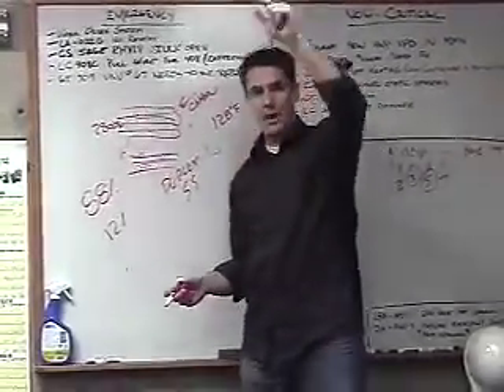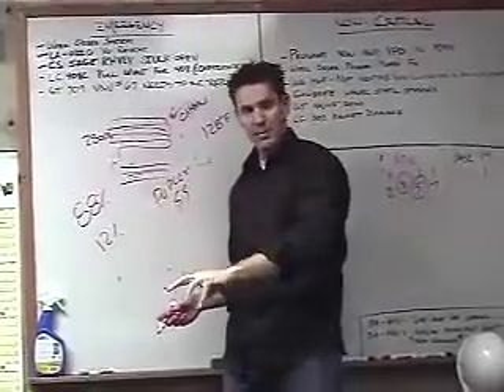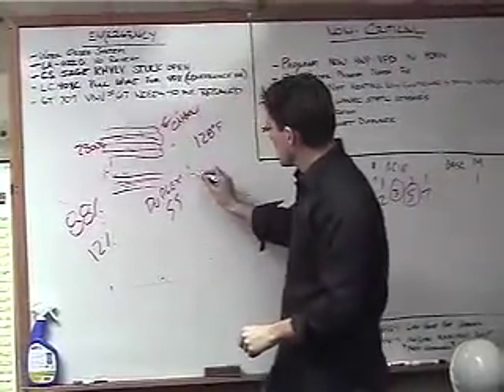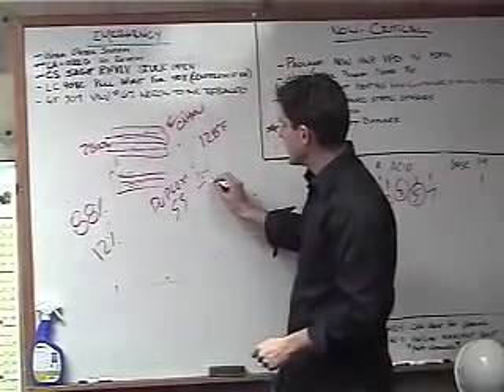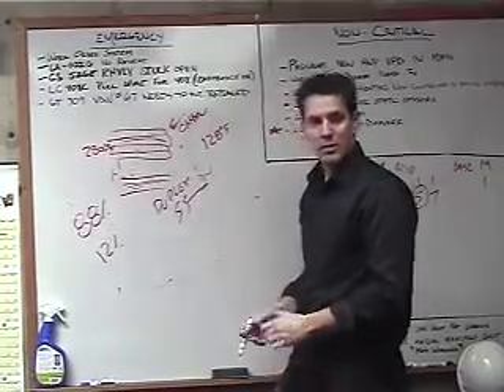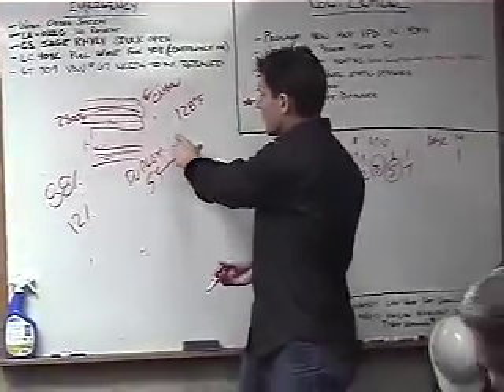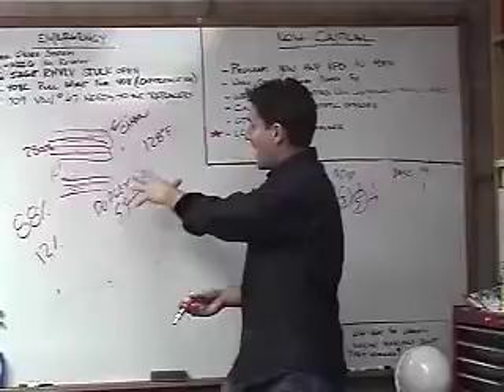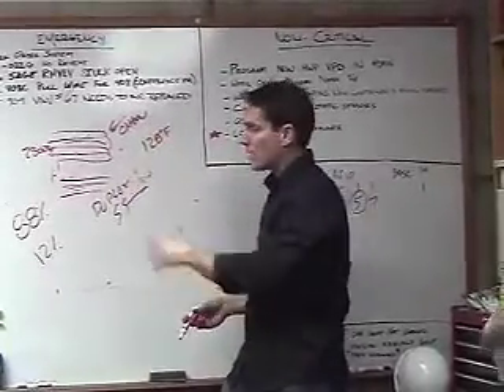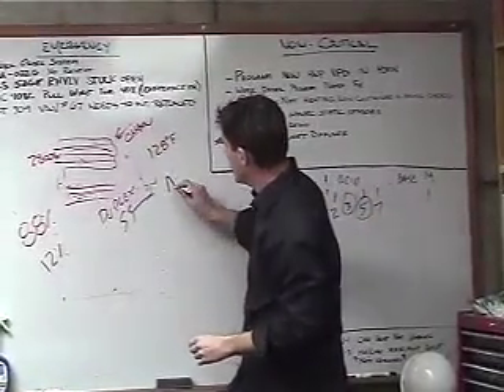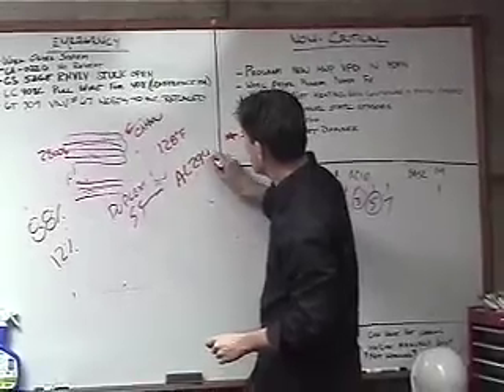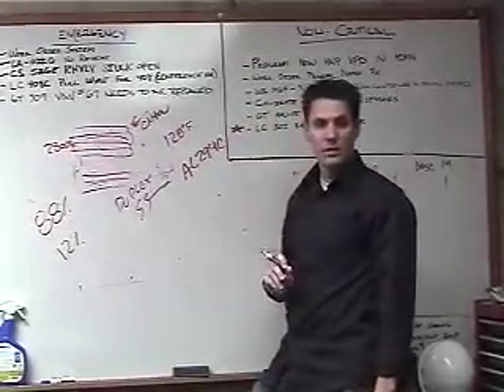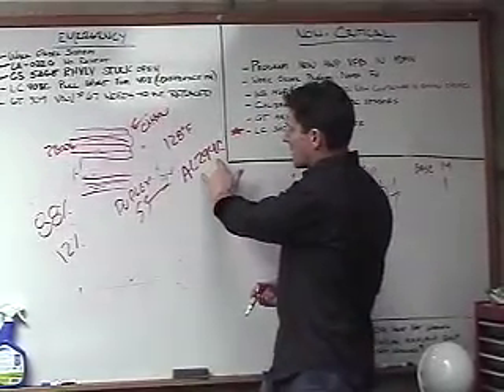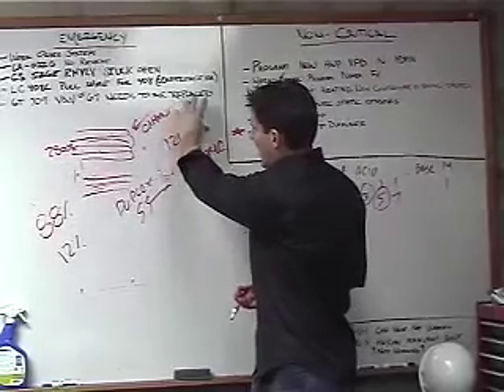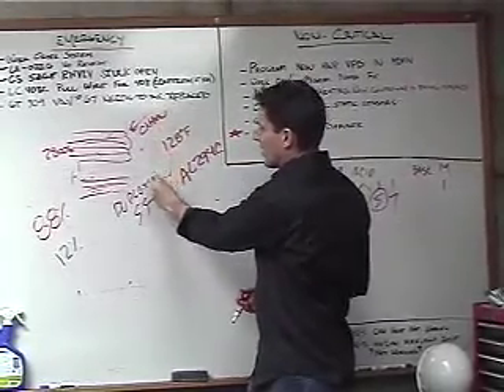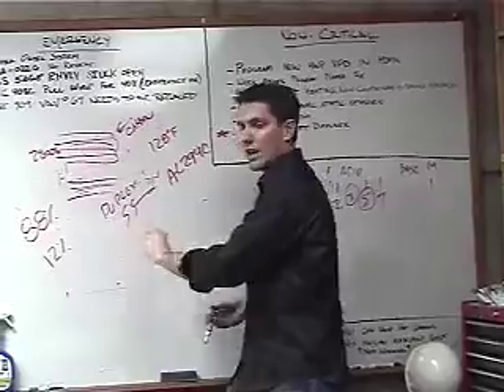If you've been around the back side of these boilers, you'll see some hoses that come out the back. Also, coming off the T here, we've got a drain T, and that's coming over. We're running the condensate that's forming because we're raining inside this stack. We've got acid rain in here, which is why your stack has to be constructed out of AL294C per code. So this is a very high grade of stainless. So it's raining acid in here. We try to collect all this acid into one point.